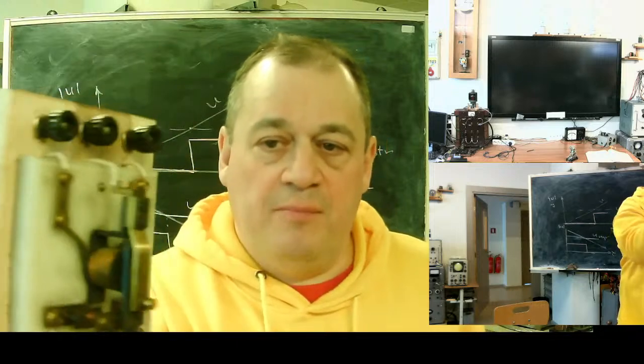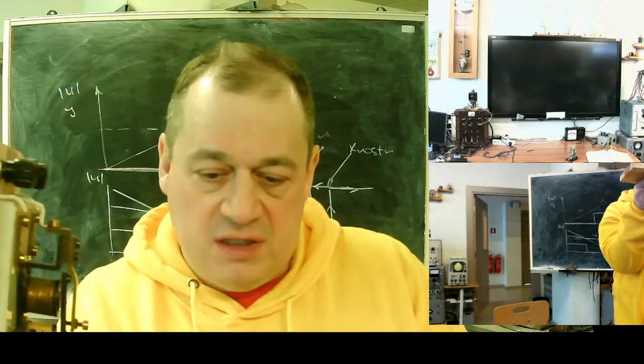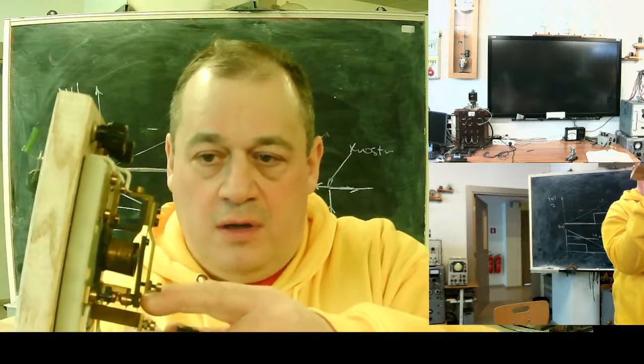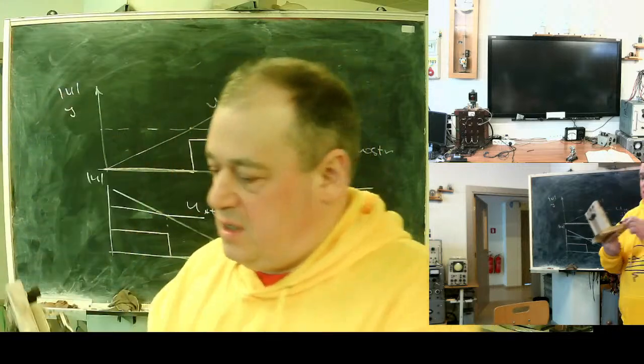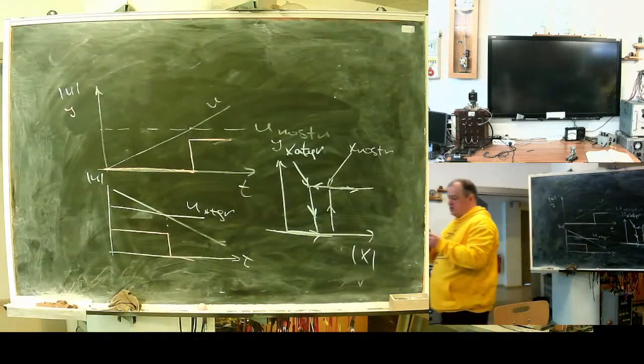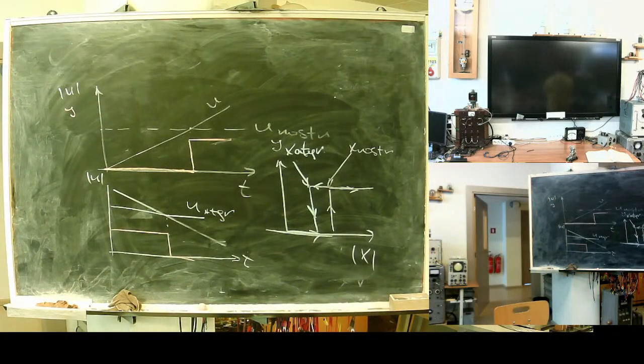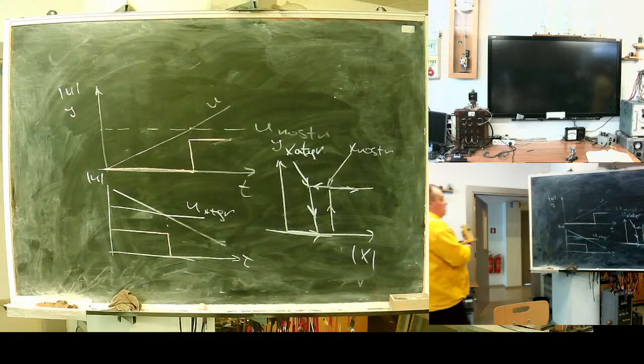I can show it close. Marble foundation. Nice. Copper and that. It's approximately 100 years old. Marble base. And current, nice contacts. For this kind of relay, if you test it, you will find a triple ratio between trip and return.